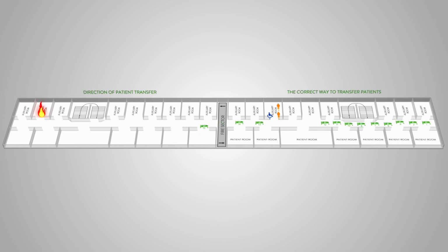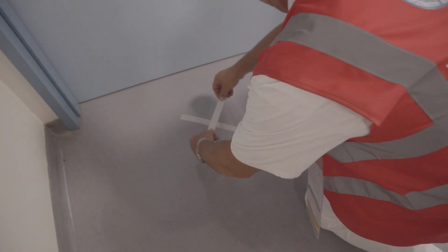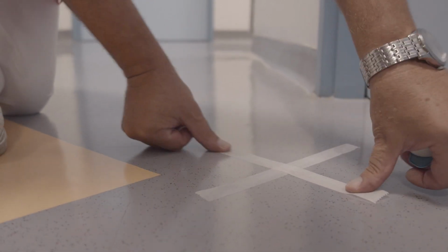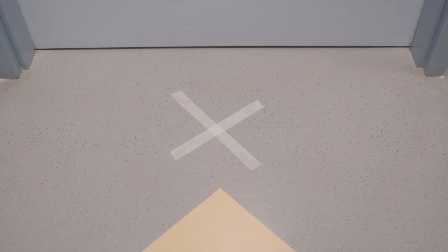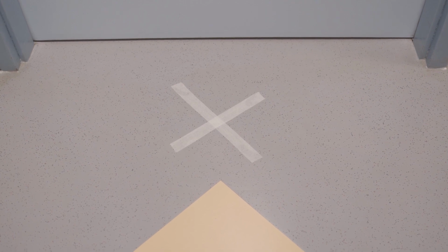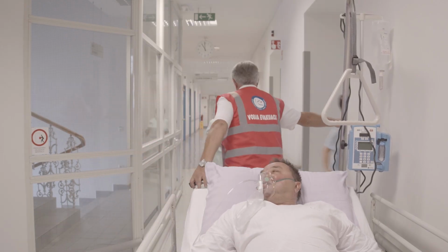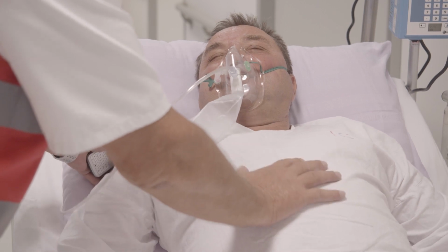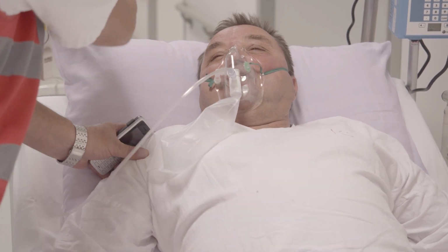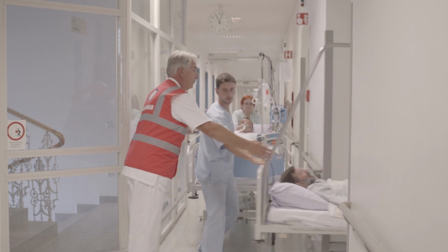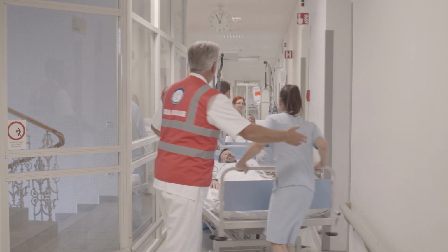When evacuating patients from the room, close the door behind you. As a rule, the person responsible for extinguishing initial fires and evacuation designates the door leaf and the floor in front of the door with a slanted line, thus indicating the evacuation is in progress, and once the evacuation from the room is completed, writes the letter X. If there are no markings, it means that the evacuation from this area has not yet begun. The lines can be made using a felt tip pen, micropore tape, or any other means.